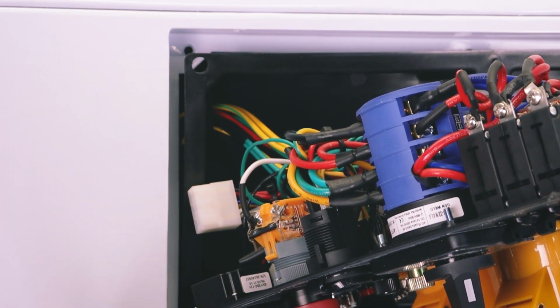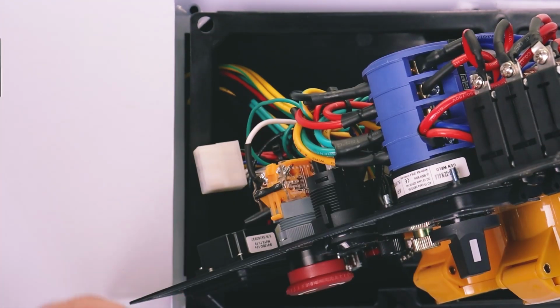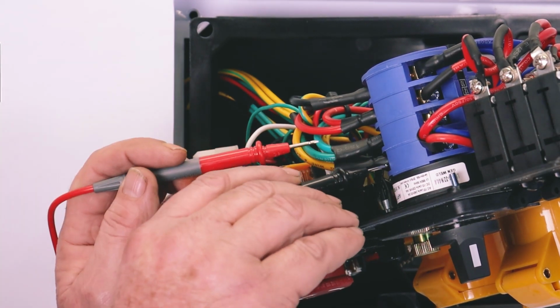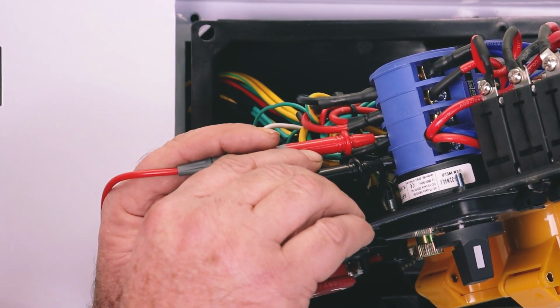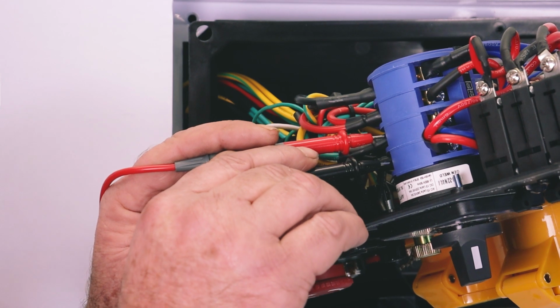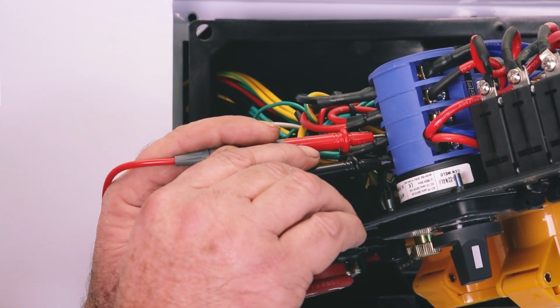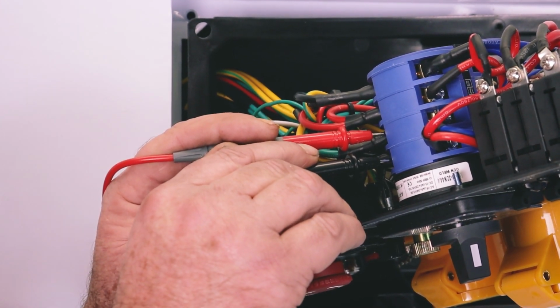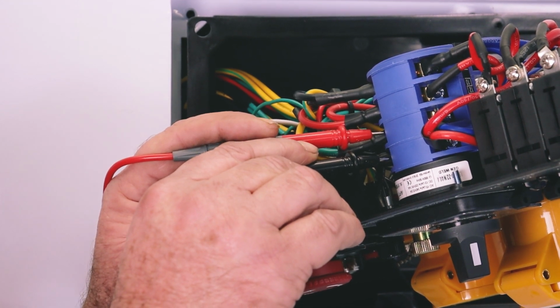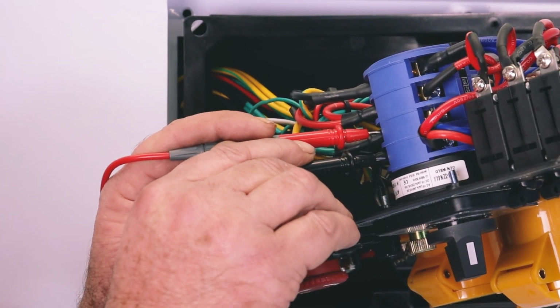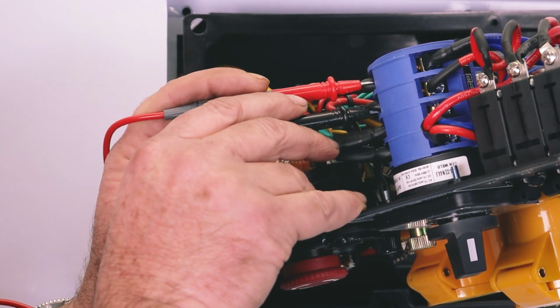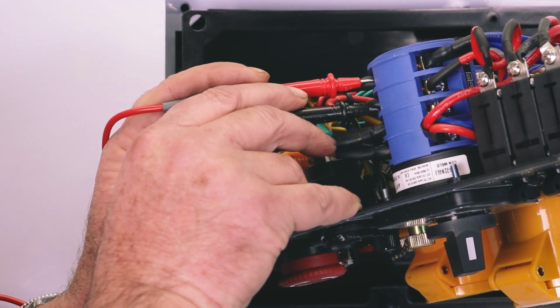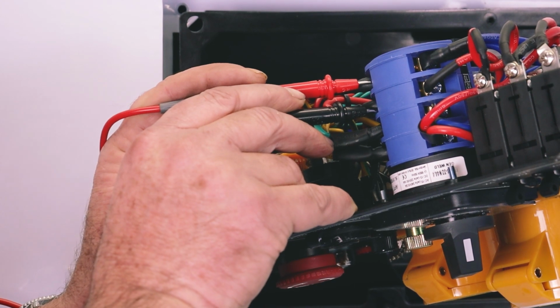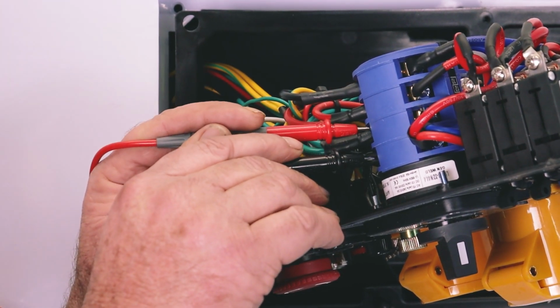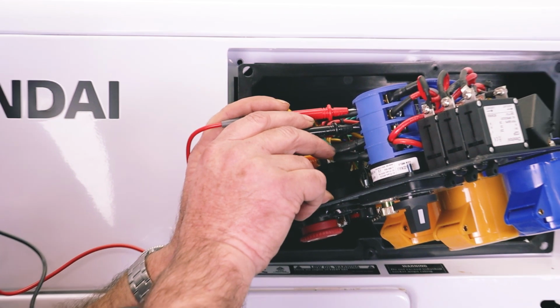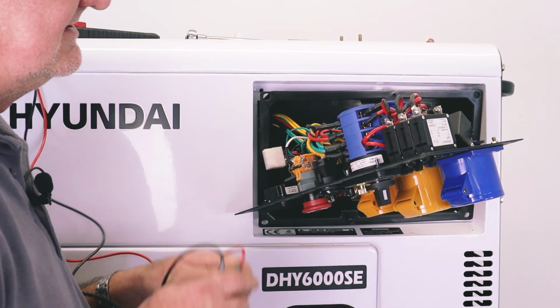So we would start the generator up again, and as I say, making sure not to touch anything at all. And you can probe across with your multimeter set on AC voltage and just see if you were getting any voltage across these two. We'd expect to see around 115, a voltage greater than 110, less than 120, shall we say. And again, we'd expect to see the same on these two. So probably around 110 volts, I would have thought, is normal. So 110 there, maybe 115, 110 there, maybe 115.